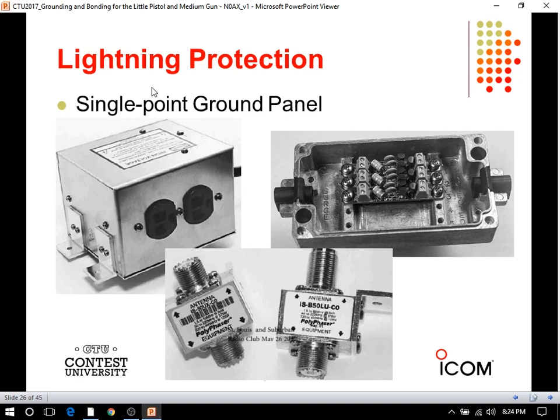Here's what an antenna protector looks like, this one from Polyphaser - you connect your feed line to this and mount it on a grounded panel. Here's another little Polyphaser gadget, this one for rotator controllers: you bring in your rotator controller on this side and hook up the control box on the other side. It's got gas discharge tubes and little MOVs that clamp the voltage at about 100 or 200 volts.